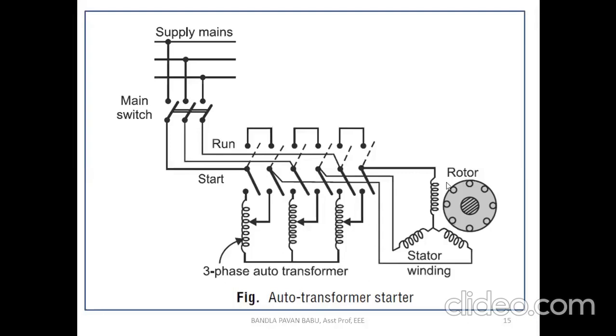So during this process, at starting we limit the current by using these inductors. Of course, these are also inductors connected in each phase. So it is nothing but an auto transformer. With a certain tap ratio, we give the supply to the machine, and soon after reaching the rated parameters, we supply the full voltage. Once the machine reaches rated parameters, it is not a big issue to provide full voltage. So this is how we limit the current and start the machine. This is also one of the efficient methods.